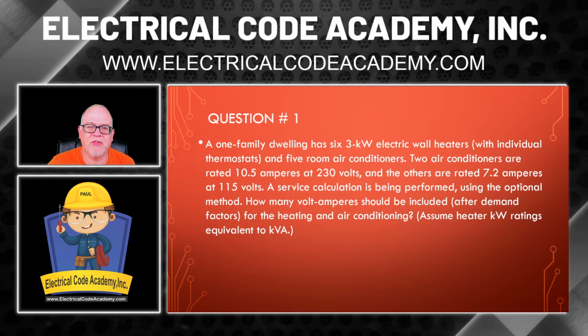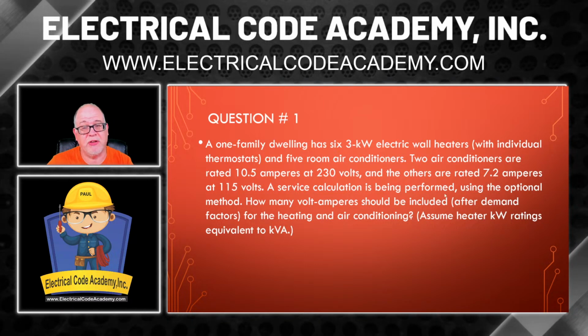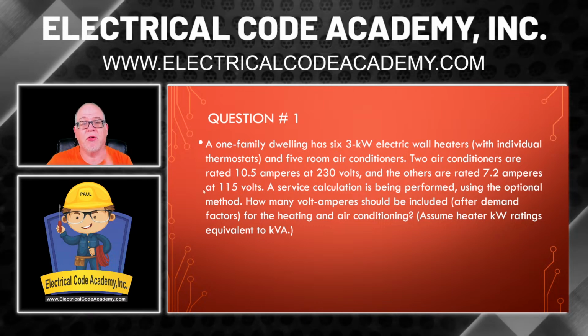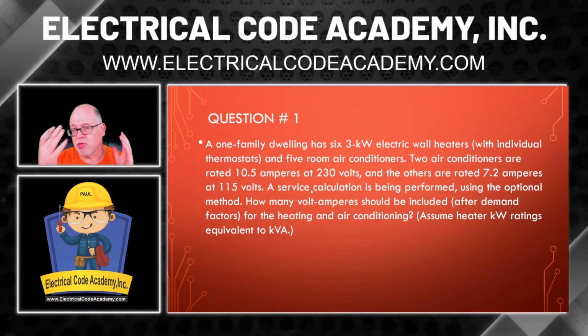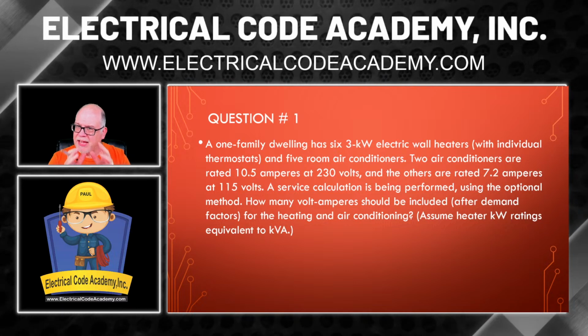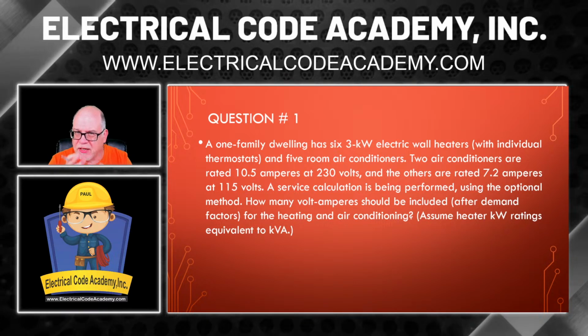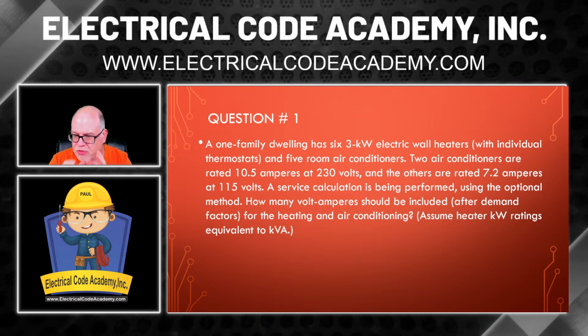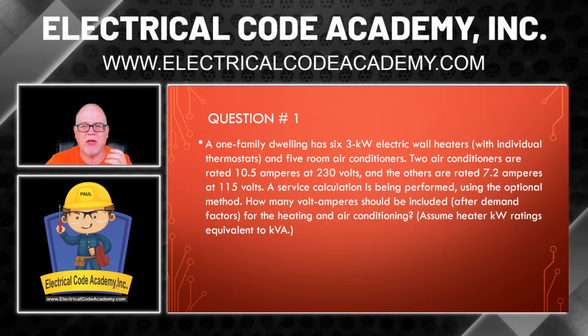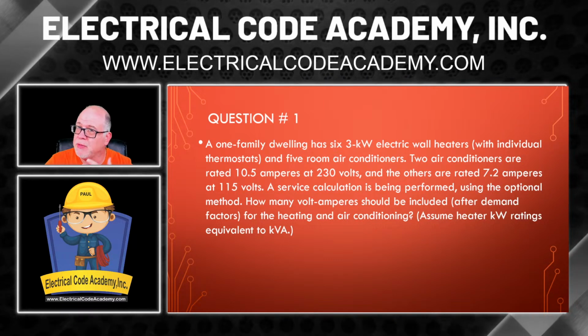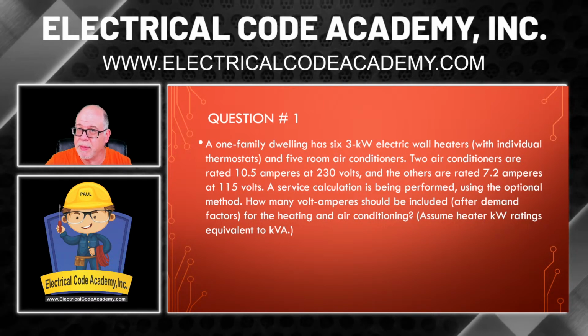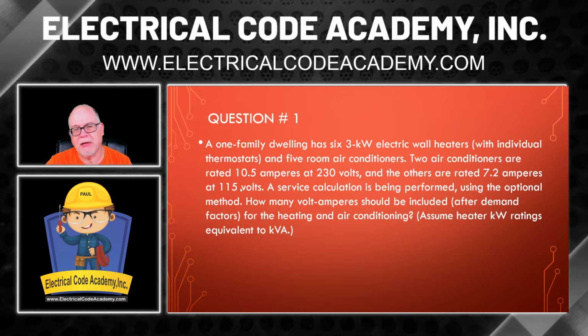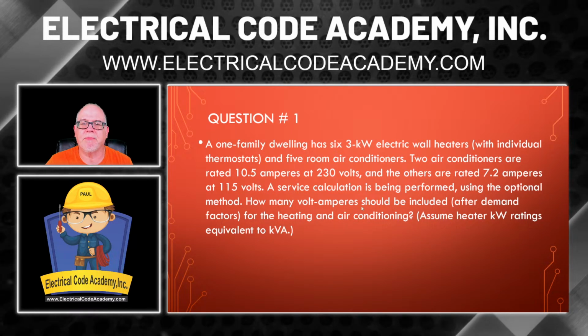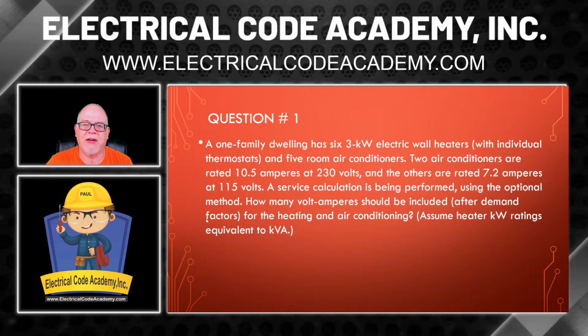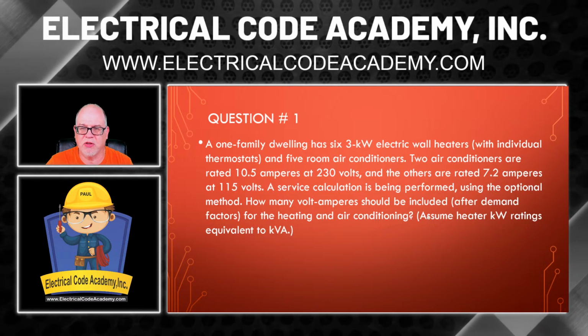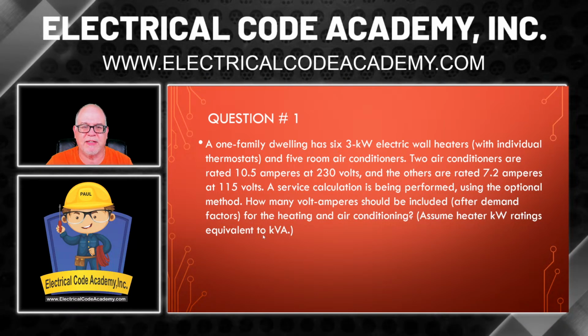All right, now it goes on to say, a service calculation is being performed using the optional method. So they'll be using the optional method to do their overall service calc. But it seems like we're only being asked to do the AC and the heat and compare the two. It is reminding you that they're using the optional method, so that puts you in the optional area, part 4 of 220. It says, how many volt amperes should be included after demand factors for the heating and air conditioning? Assume heater kW ratings are equivalent to kVA.